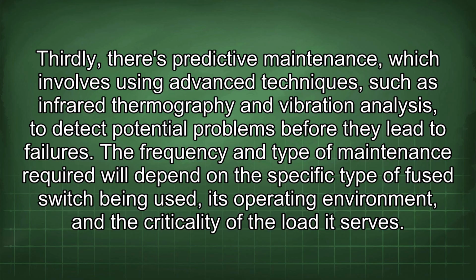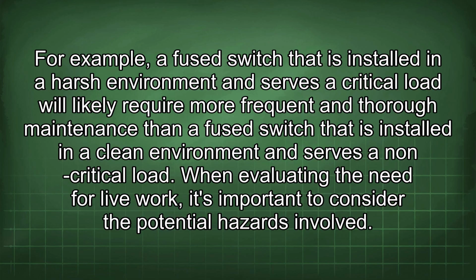The frequency and type of maintenance required will depend on the specific type of fuse switch being used, its operating environment, and the criticality of the load it serves. For example, a fuse switch that is installed in a harsh environment and serves a critical load will likely require more frequent and thorough maintenance than a fuse switch that is installed in a clean environment and serves a non-critical load. When evaluating the need for live work, it's important to consider the potential hazards involved.